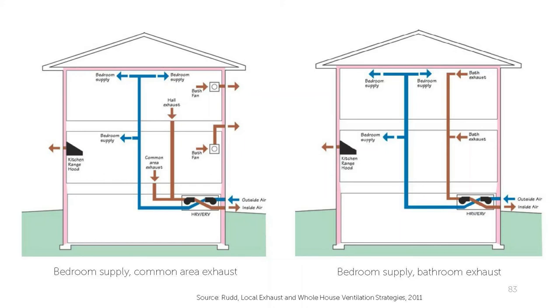Speaking of comfort, the following strategies can help. Supply smaller amounts of air to more locations with the air entering the room at or near the ceiling, and use grills that cause the supply air to mix quickly. Too much air moving too fast over people feels uncomfortable, even if that air is at room temperature. Avoid supplying fresh air too close to a door opening or to returns to ensure proper mixing. Air temperature leaving the ventilator should be as warm as possible and can be accomplished with a high efficiency ERV or HRV.